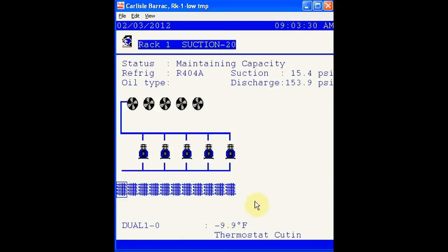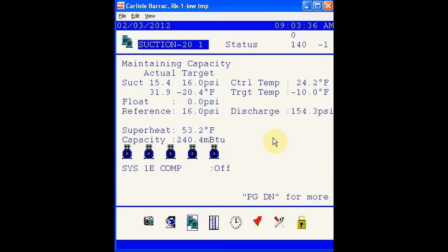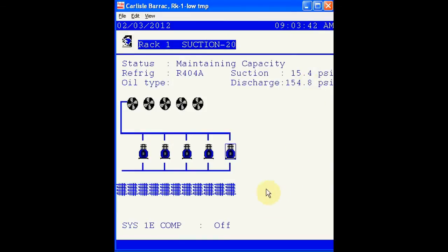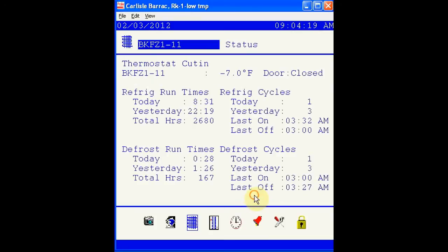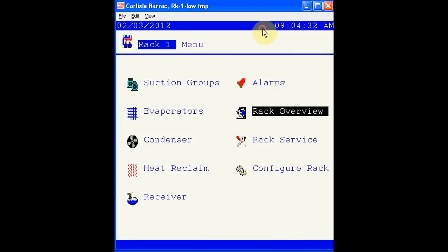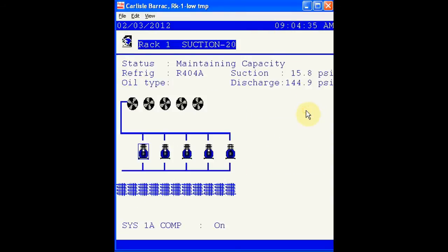It's possible to get more details on any of these items by selecting it. To back up, escape will take you back to the overview. We can get more details by selecting an evaporator, paging down. Here you'll find defrost runtimes, refrigeration runtimes, cycles, last defrost cycles. Let's back up, take a look at the rack overview screen, and see the cycles and runtimes for condenser fan relay number 5.